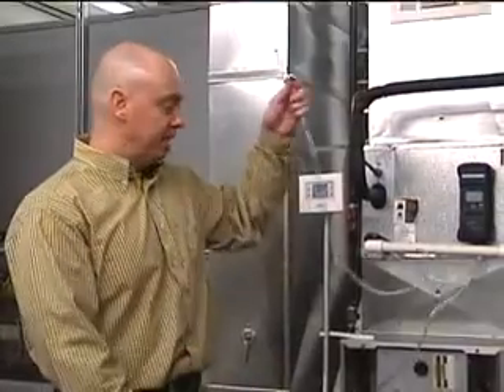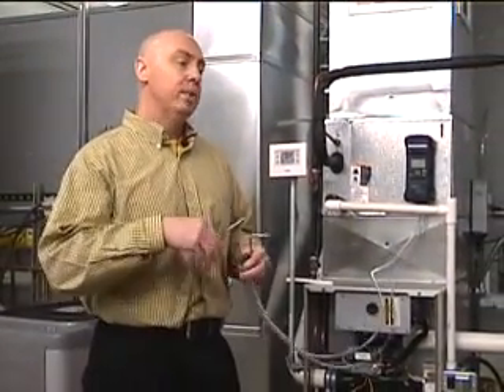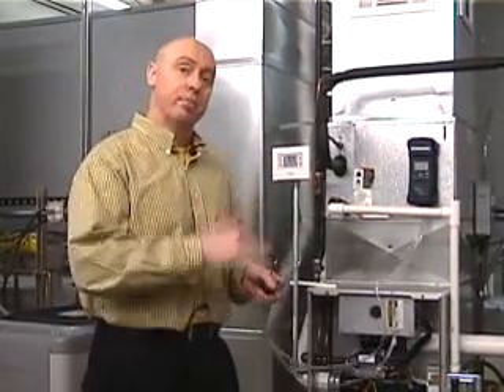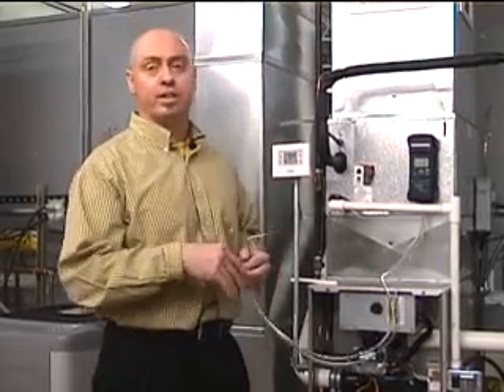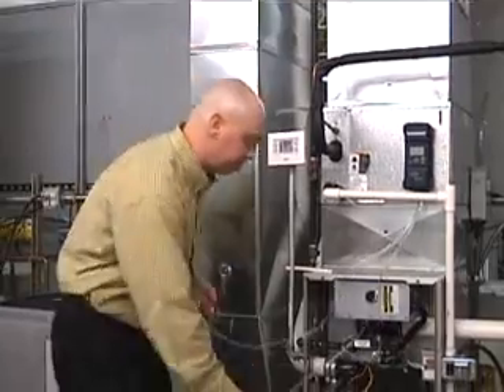I can also take the same setup, and you have to be careful with filters. Filters can have a high pressure drop across them too. High pressure drop filters are typically never a good idea. We see that a lot because homeowners tend to go out and buy filters they hear about on TV or something like that, and you can get a very high pressure drop across them. Some of them work to some degree, but very highly restrictive filters are typically not a very good idea.